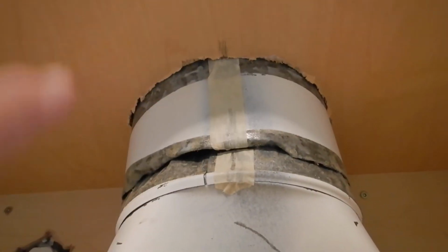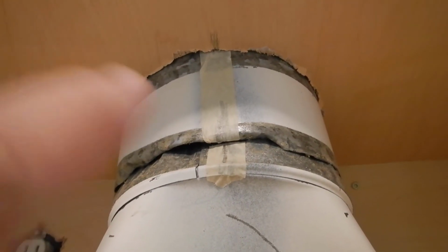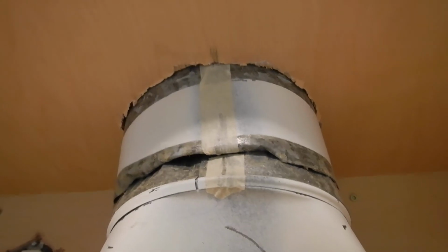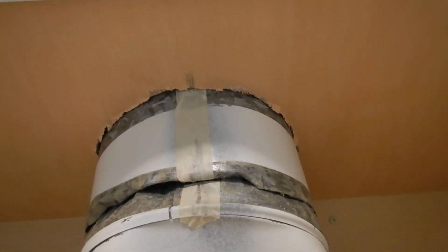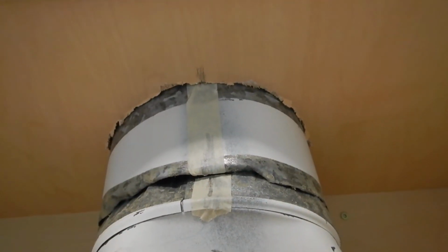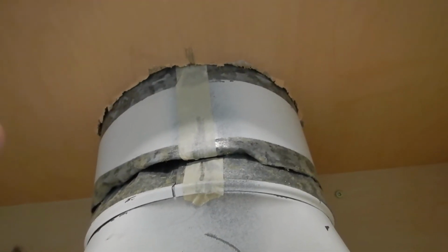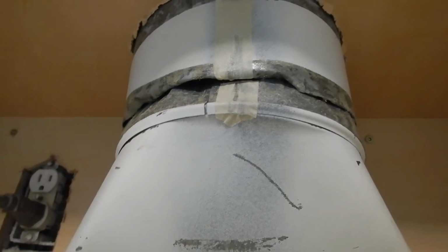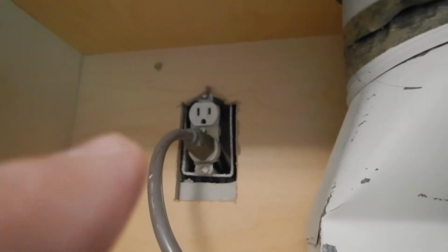You're also supposed to have a fire blocking plate around here, and not a bunch of silver tape either. I've seen people cut the tape in squares and patterns, really try to fake it in there, but no, it needs to be a metal plate, a galvanized metal plate. So we need a fire blocking plate, and we need this gap to be sealed up. And the electric receptacle outlet cover plate should have been replaced. That's what we need.